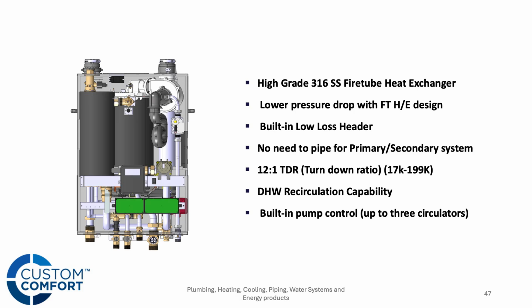So walking down some more of these benefits here, 12-to-1 turn down ratio, right? It's a big boiler, it's 199,000 BTUs, but it's going to modulate all the way down to under 20,000 BTUs. I think 17,000 BTUs on the low end. So again, we're sizing for the domestic need here, knowing that the heating side can ramp down to under 20,000 BTUs. You want to do domestic hot water recirc, we've got a dedicated recirc tapping on this. So pipe your recirc line directly back to this boiler, and it's going to make sure that you've got hot water at all times.